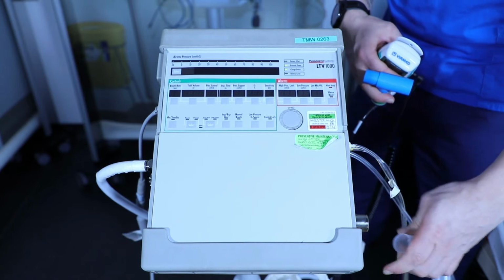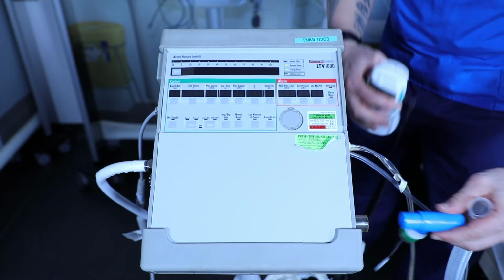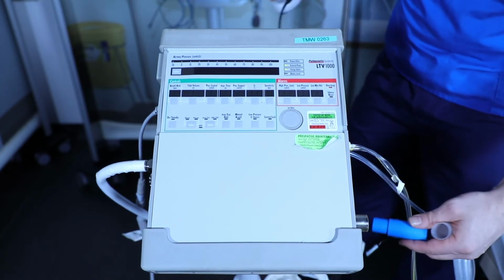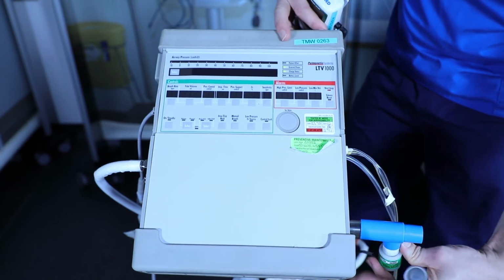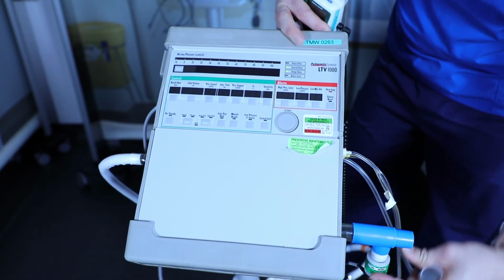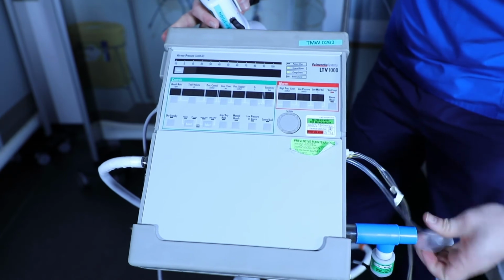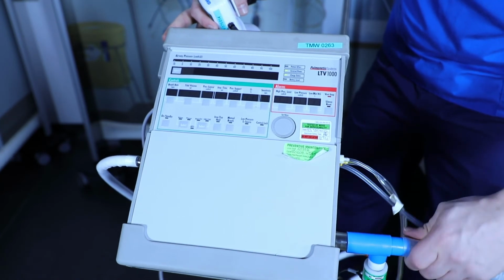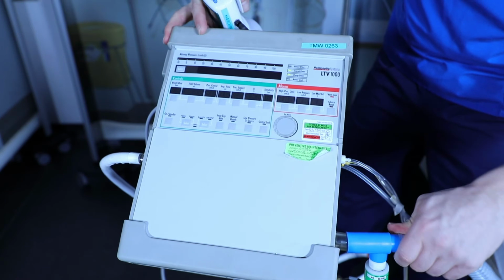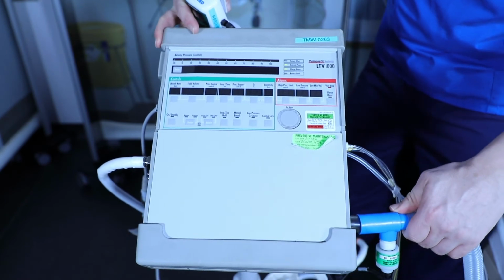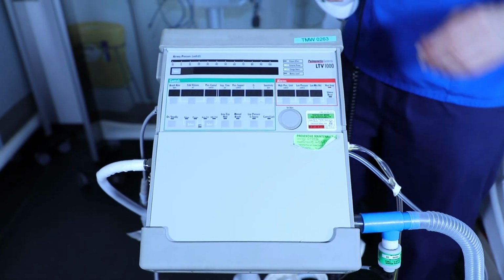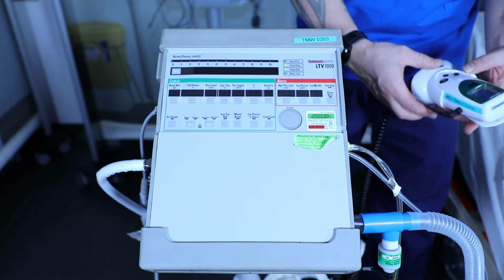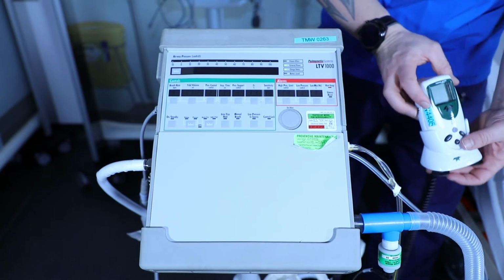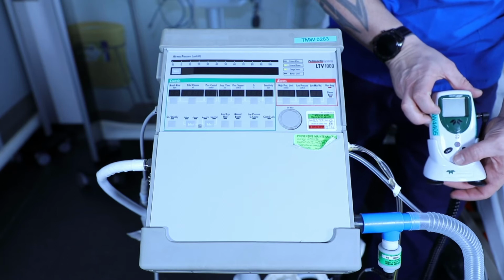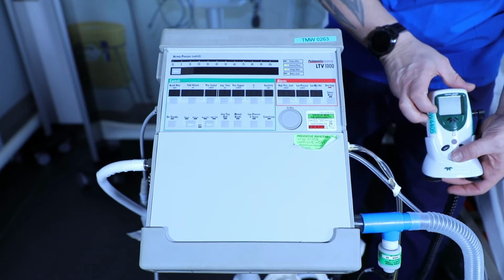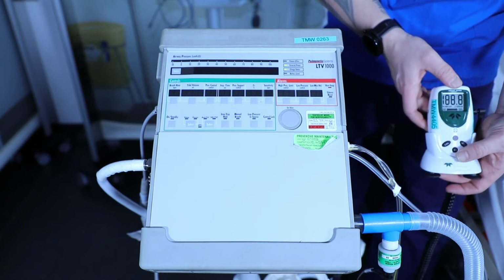So if we disconnect the patient circuit, on your O2 analyzer there should be a T-piece, which connects up where the patient circuit goes, and then we reconnect the patient circuit here. The O2 analyzer then just needs to be switched on, and of course this would be calibrated, but like I said, this won't be covered in this particular video.